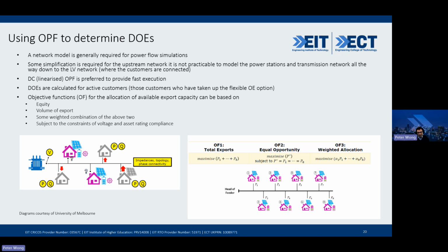If you model the whole thing, from the central power stations to the low voltage, there's a lot of network you're trying to model. That means the power flow is going to be complicated and take a long time to do. Because you want a dynamic operating envelope that you can convey to the customers, to the end devices, to operate on a real time basis, you really can't have the network so extensive, or computation takes too long. So you need some simplification of the upstream network, because it's really not practical to model from the power station down to the low voltage customer connection point, since we want speed of operation. So really a linearized OPF is preferred, because we want fast execution.